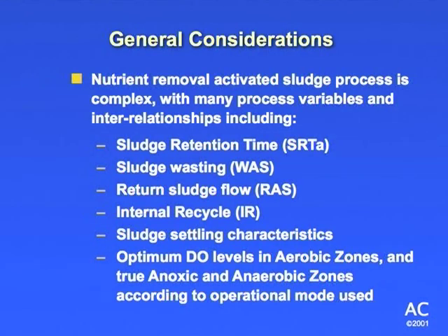Okay, and of course, here you've got to be concerned about optimum DO levels in the aerobic zone. Well, that's something you've been doing all along. But now you've got to worry about true anoxic and true anaerobic zones according to the operational mode used. So you will be monitoring to make sure that you keep those zones truly an anoxic zone or truly an anaerobic zone. There's no oxygen or nitrate in that anaerobic zone.